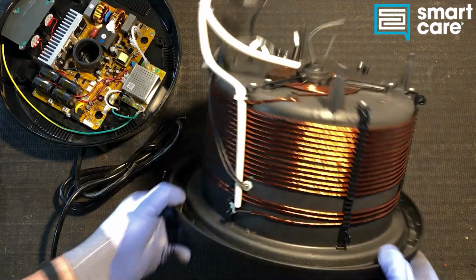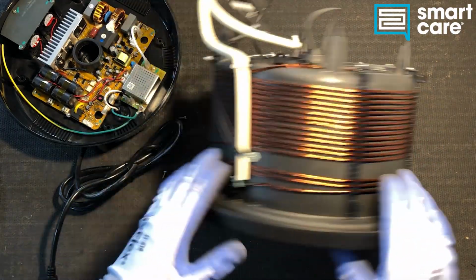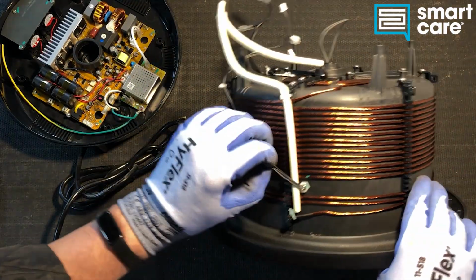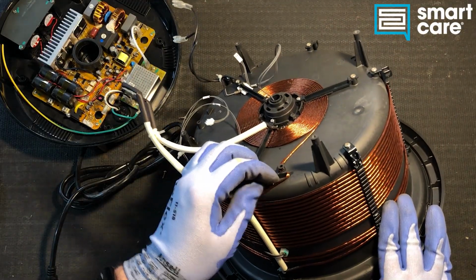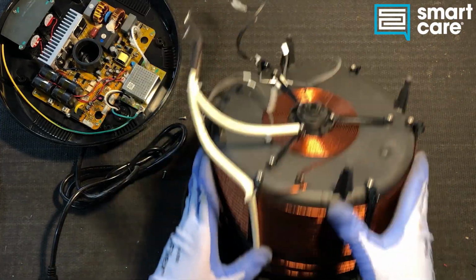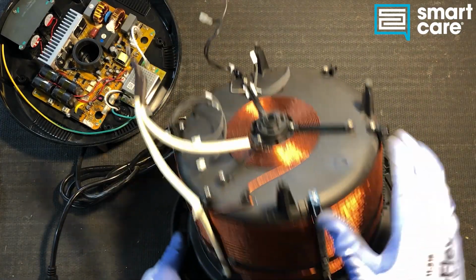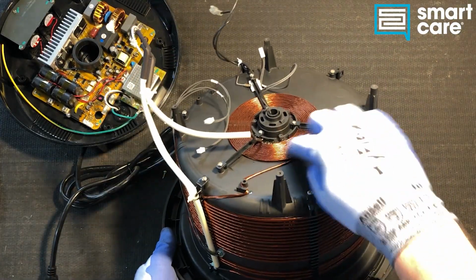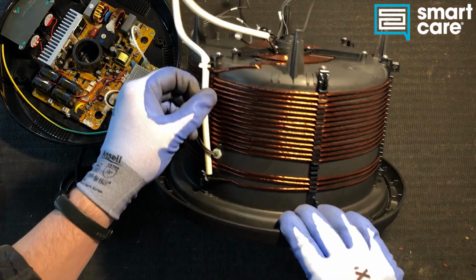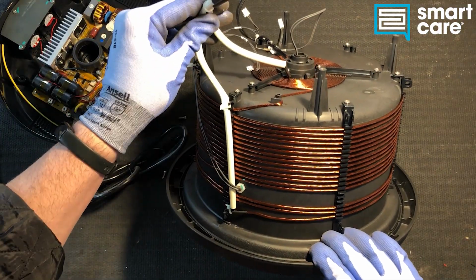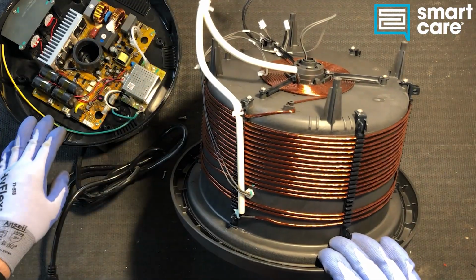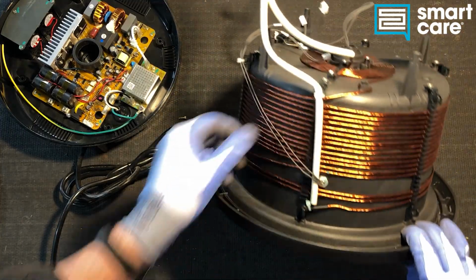You can see right away it's a pretty incredible winding of coil. We've got a heavy gauge copper, bare, uninsulated, and it wraps around this thermoplastic insert from the sides, from the bottom. Then it's got a piece of insulation over the ends where it runs back down to our control board. You can see these are temperature probes.